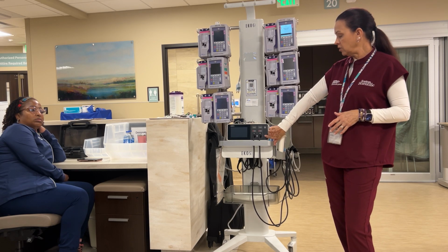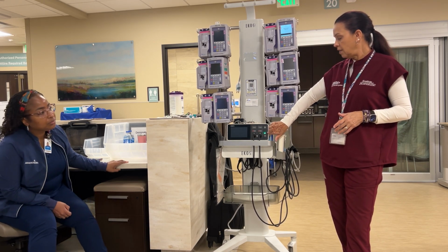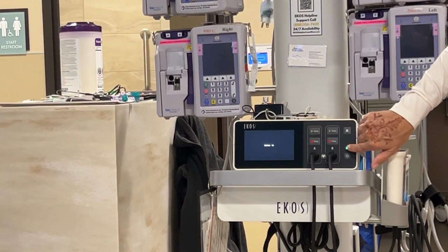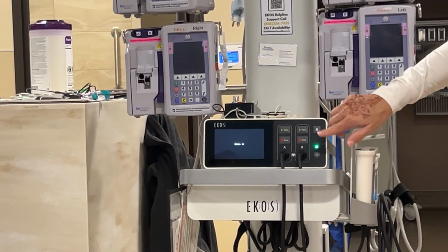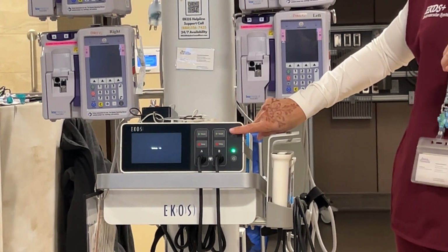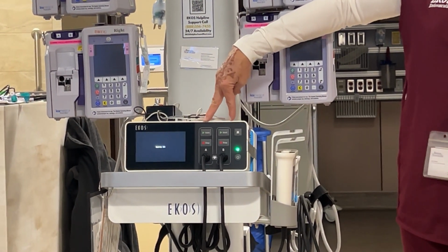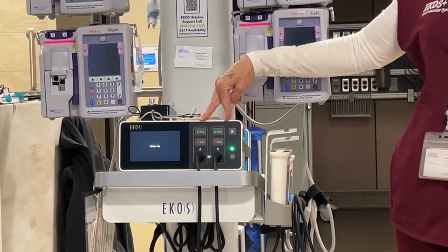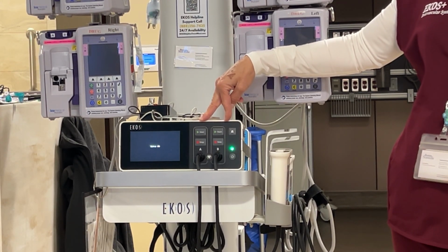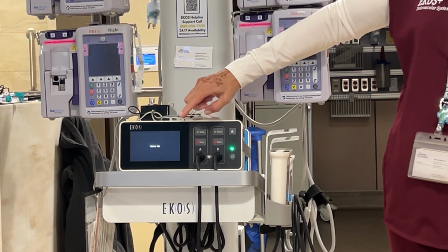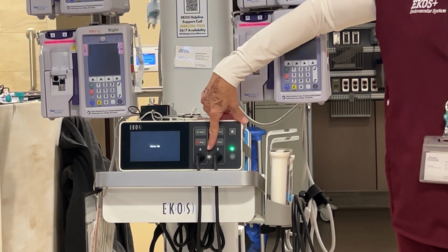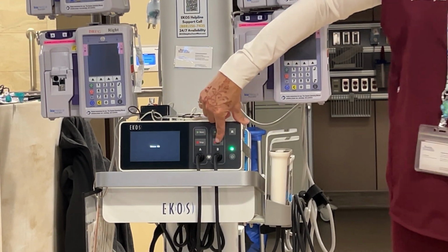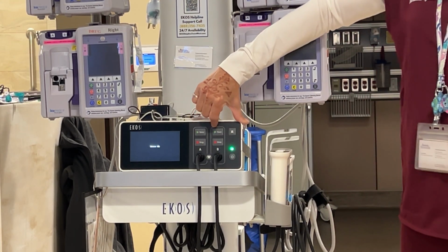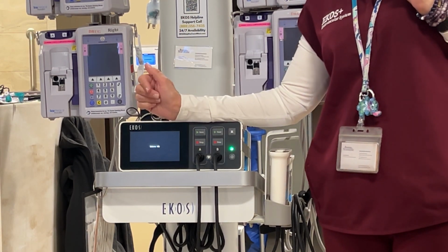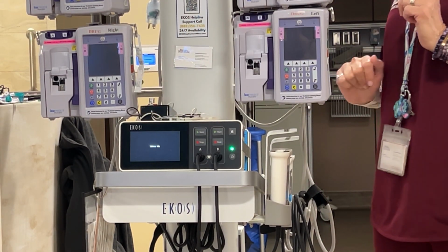So the main power switch is down here in the corner. The green light comes on. That just means there's power to the unit. Above that is your mute or your audio pause button, as they like to call it. Dual channel capability. We can run 1 or 2 catheters with this machine. Your start, your stop, channel A, channel B. The heart signifies that this equipment is defibrillator compatible, meaning if your patient is being shocked and you are close to or leaning on it, you will not get shocked.